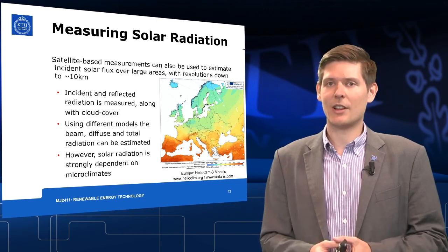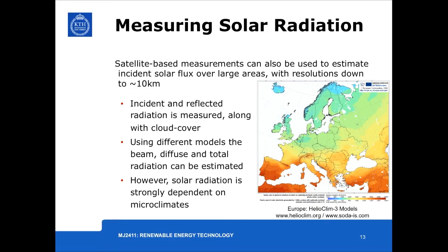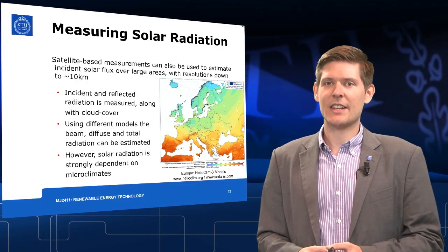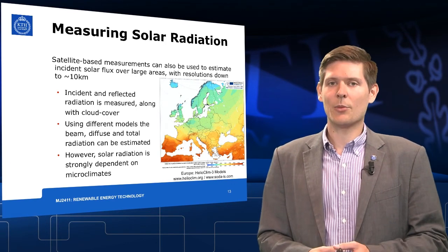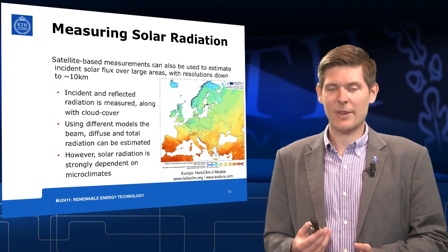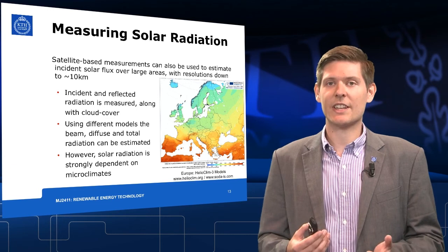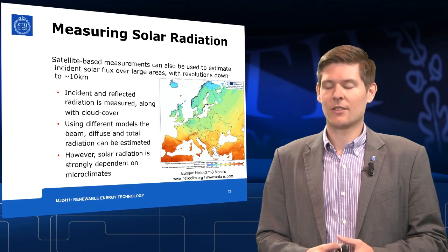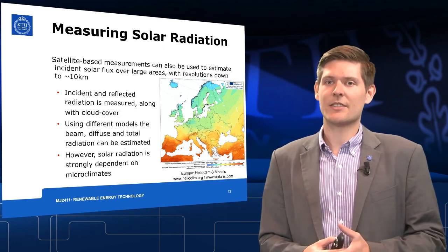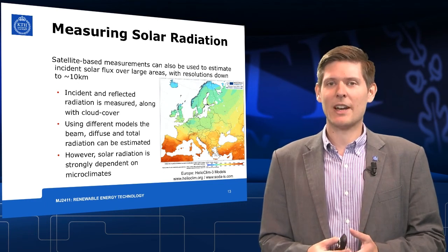And finally, we have large-scale measurements. We use satellite measurements in order to measure the solar radiation for big scales with a resolution of down to about 10 kilometers. The incident and also the reflected radiation are measured along with cloud covers. Using different formulas and equations and models, you can calculate the beam diffuse and also the total radiation. However, it is very important to point out that these models have weaknesses. The solar radiation on site is strongly dependent on the microclimate.